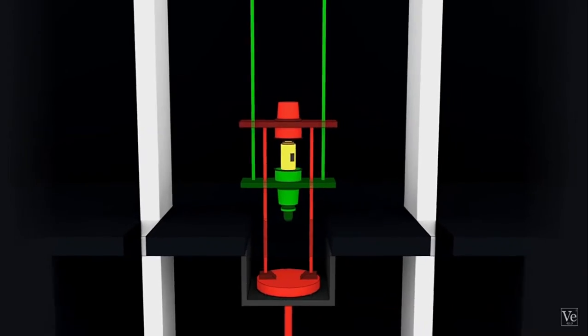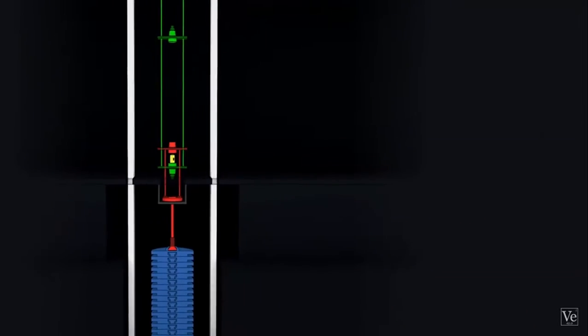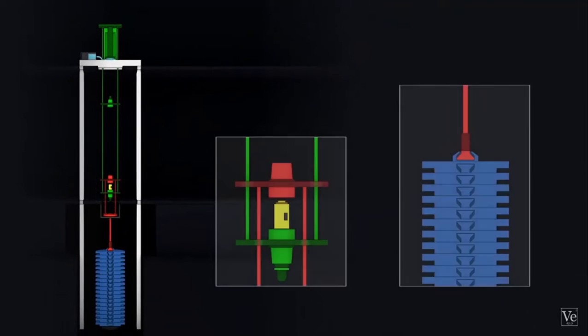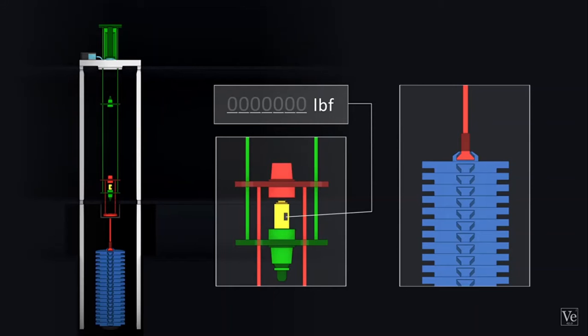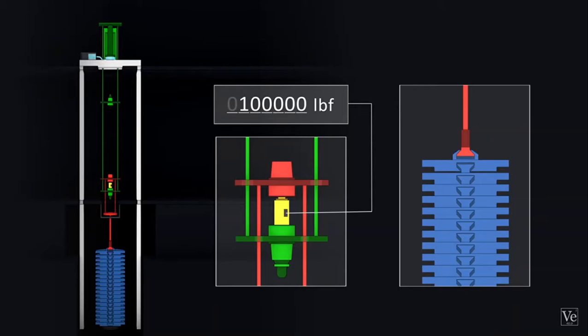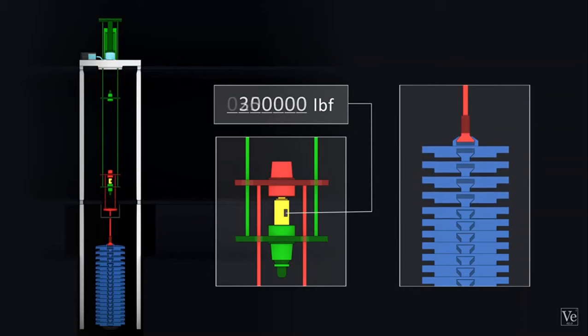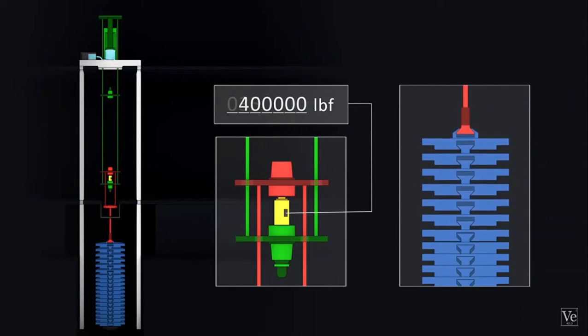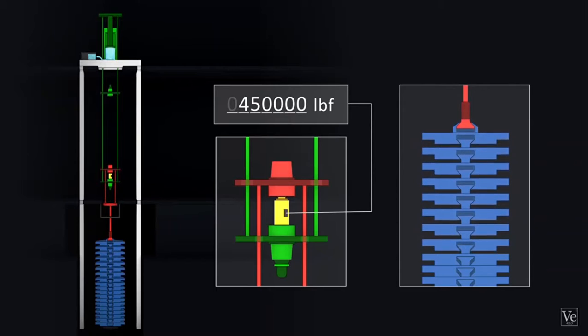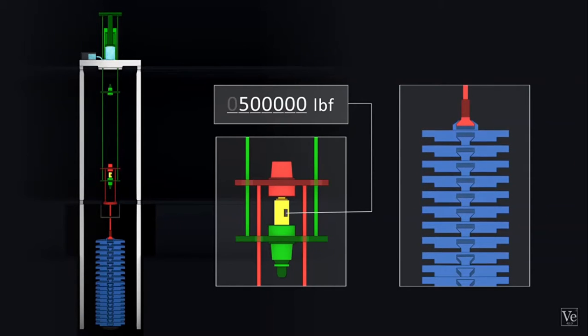One of these would be placed on the compression head right here. Then a hydraulic ram in the attic starts to raise the green lifting frame. And once the force transducer contacts the red loading frame, well then it starts lifting the weights downstairs. And as the lifting frame continues to rise, more and more of the 50,000 pound weights become suspended by the force sensor. And since the weights create an accurately known force, the readouts from the force transducer can be precisely calibrated. These devices are then sent out into the field.